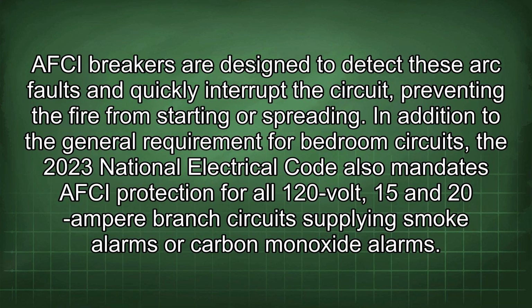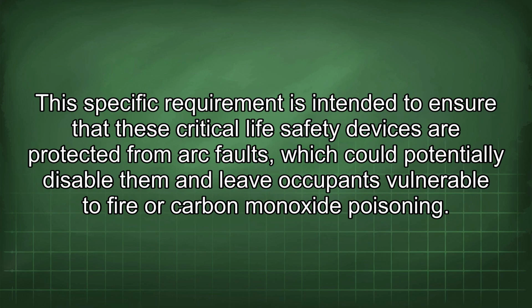AFCI breakers are designed to detect these arc faults and quickly interrupt the circuit, preventing the fire from starting or spreading. In addition to the general requirement for bedroom circuits, the 2023 National Electrical Code also mandates AFCI protection for all 120-volt, 15 and 20 ampere branch circuits supplying smoke alarms or carbon monoxide alarms. This specific requirement is intended to ensure that these critical life safety devices are protected from arc faults, which could potentially disable them and leave occupants vulnerable to fire or carbon monoxide poisoning.